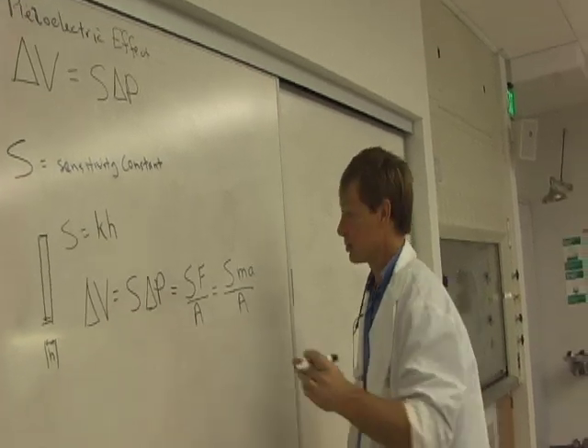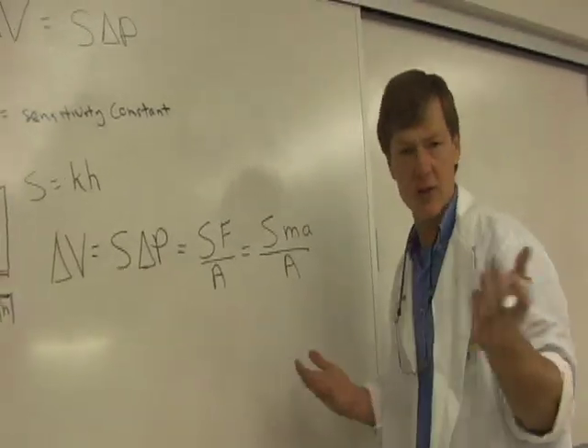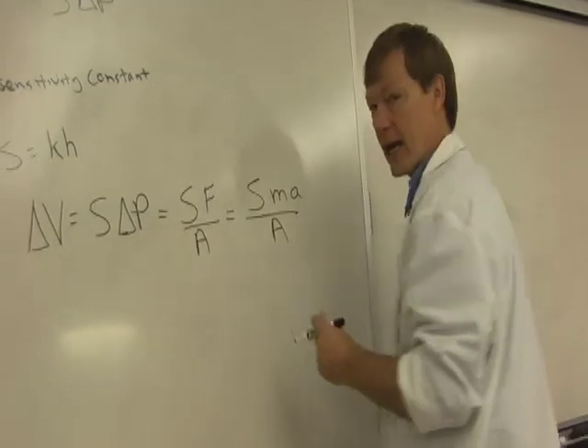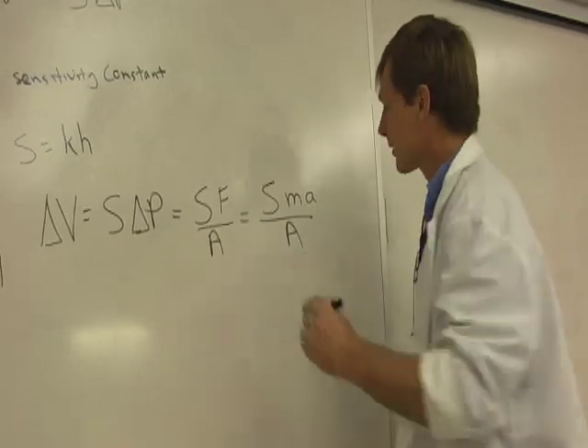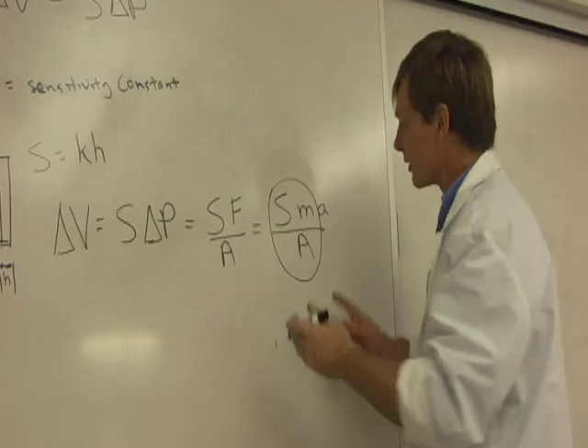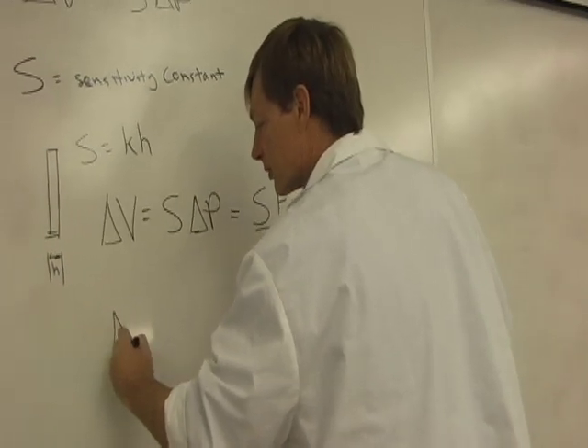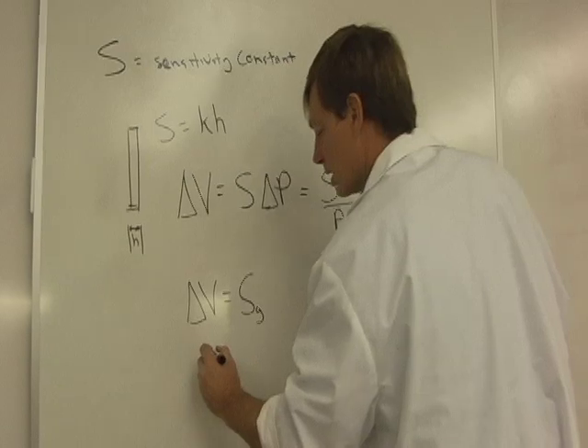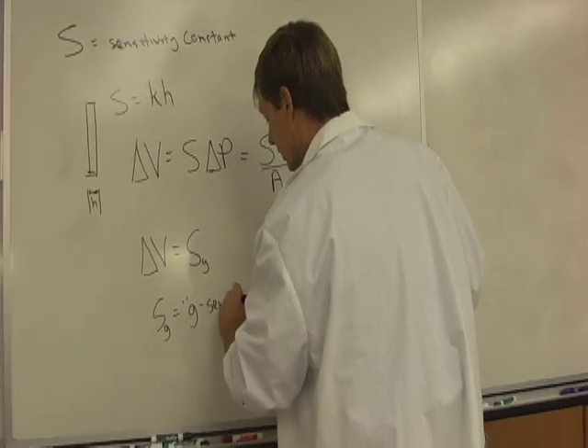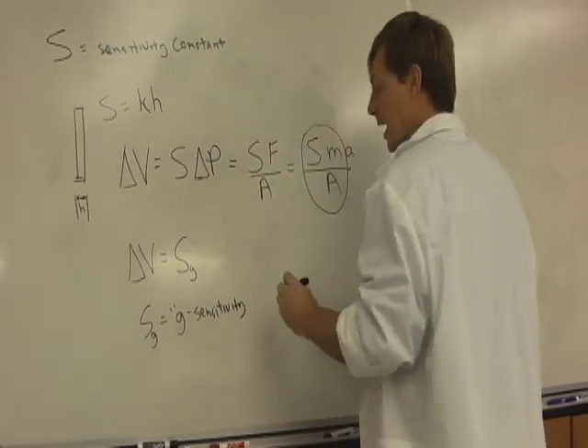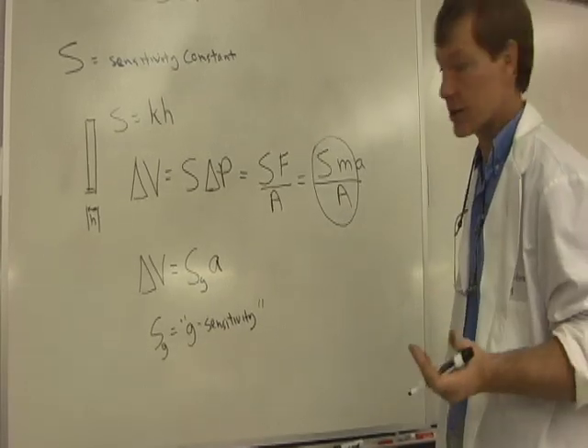For the accelerometer that I showed you, the sensitivity is set because we chose the thickness of the material. We chose the material itself. The mass is set. It's already preloaded in the accelerometer. And the area, that's the area that the piezoelectric crystal is sitting on, the size of it, that's already set. So all this in the accelerometer is a constant. So we could say, for accelerometers, the voltage is equal to the constant s of g. I'm going to call s of g the g sensitivity, because that's even funnier. So the voltage change is directly proportional to the acceleration. It's a direct correlation.